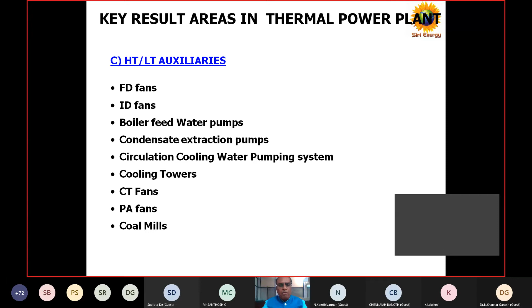Those are the equipment we further divide when we are doing the energy audit analysis in our scope. All this we will cover, and try to give an efficiency test and also a performance test, and come out with a benefit analysis, that is, the saving areas in each and every area. In addition to that, there is insulation, because in a boiler they have a lot of insulation, and there are steam lines with insulation. For all this we do the thermography test. We have a thermal imager, we do thermal imaging of all the surfaces, and we find out where the heat loss is, how much heat loss is taking place, what the existing insulation thickness is, and how much extra insulation has to be added.